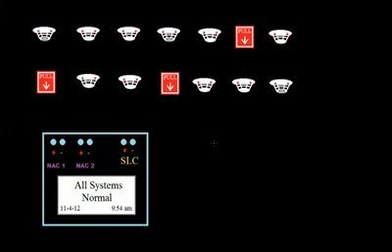But on the right, you can see I've drawn this little thing, just one circuit here, and it's labeled SLC, and that stands for Signaling Line Circuit. That's a terminology that a lot of manufacturers use, not all of them. Simplex and I think Edwards use some other ones, but the panels I primarily deal with use that terminology, and they all use some form of data communication with their devices. Whatever they call that may vary from manufacturer to manufacturer.